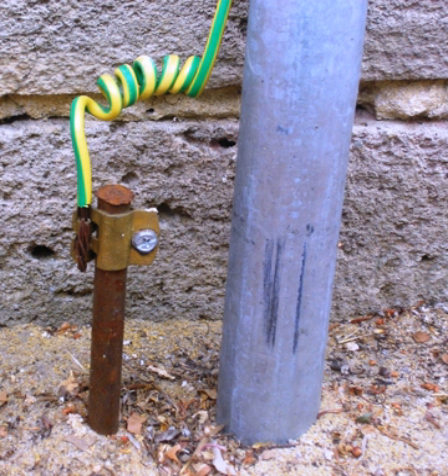Generally, every AC power line transformer acts as an isolation transformer, and every step up or down has the potential to form an isolated circuit. However, this isolation would prevent failed devices from blowing fuses when shorted to their ground conductor. The isolation that could be created by each transformer is defeated by always having one leg of the transformers grounded, on both sides of the input and output transformer coils. Power lines also typically ground one specific wire at every pole, to ensure current equalization from pole to pole if a short to ground is occurring.